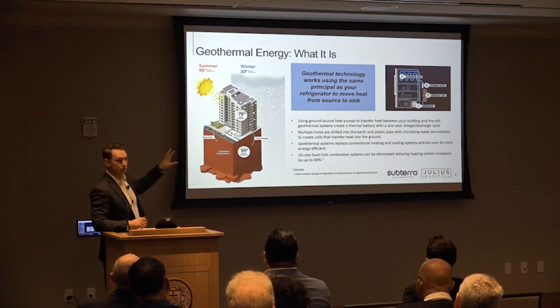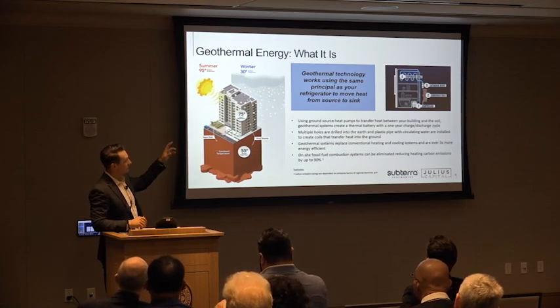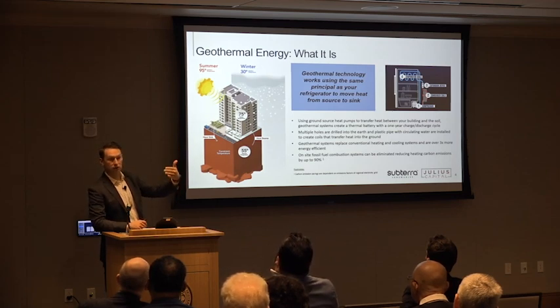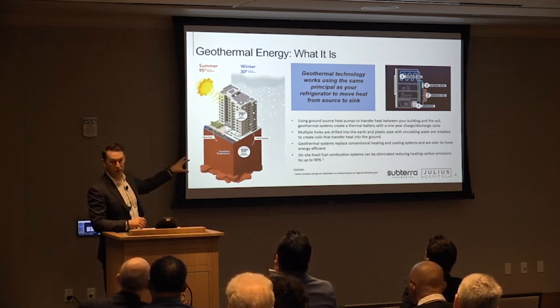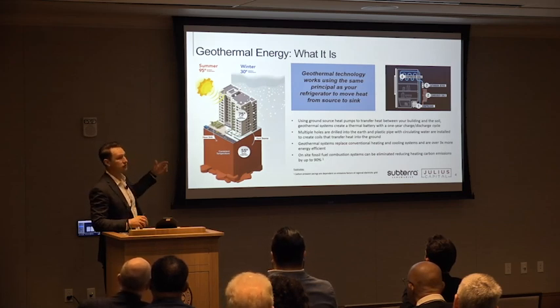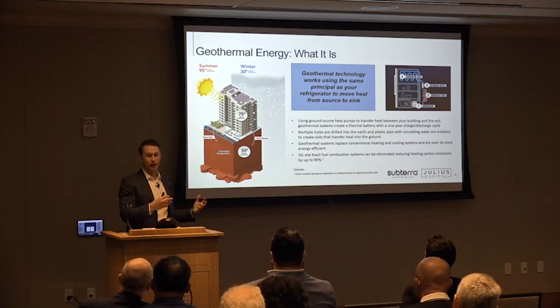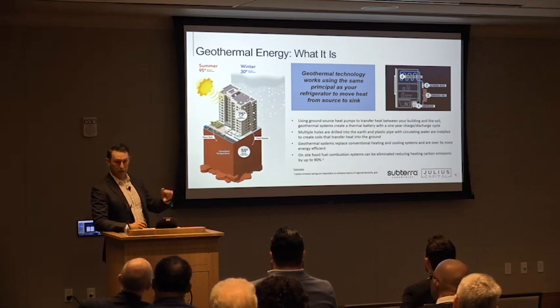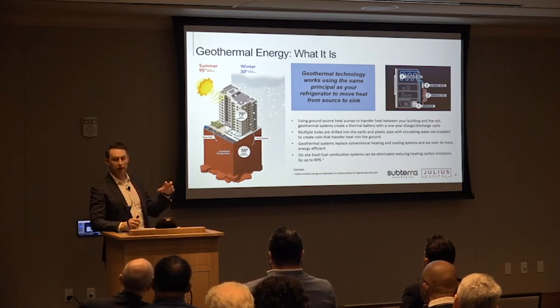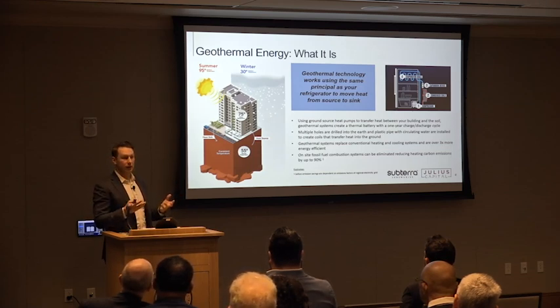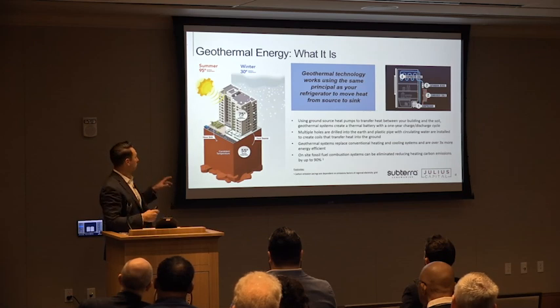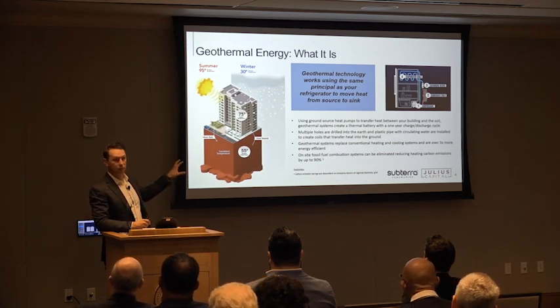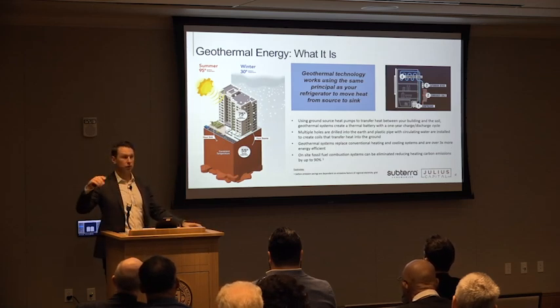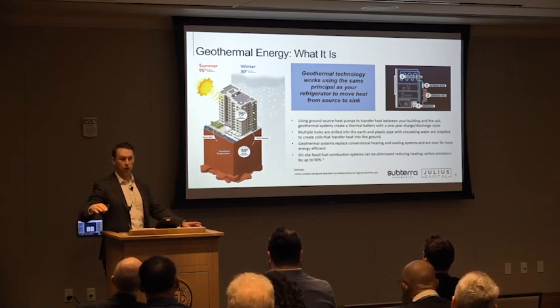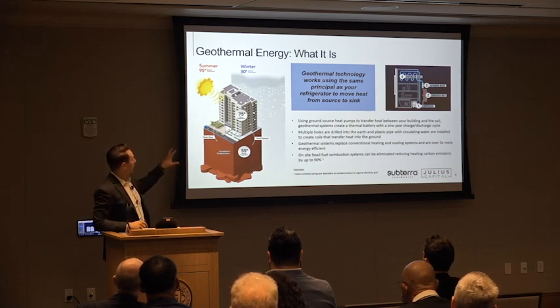A geothermal system works on the same principle, except instead of the inside of your fridge, think about the inside of your building, and instead of coils on the back of your fridge, think about coils buried in the ground. We have that refrigeration cycle moving heat from the ground to the building and back. We can reverse the cycle to move heat out of the building, cooling it and increasing ground temperature. In winter, we pull that heat back out of the ground into the building to heat it. So it becomes a thermal battery using the volume of soil under your building, with a one-year charge and discharge cycle, constantly raising and lowering ground temperature. That's the principle driving this geothermal system.